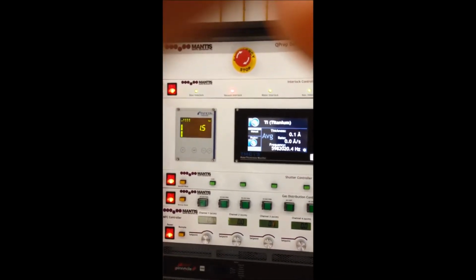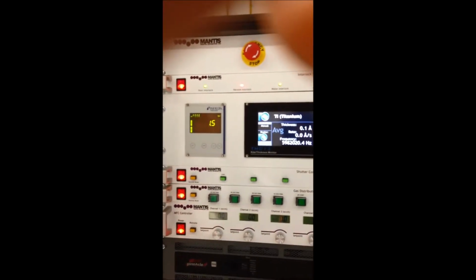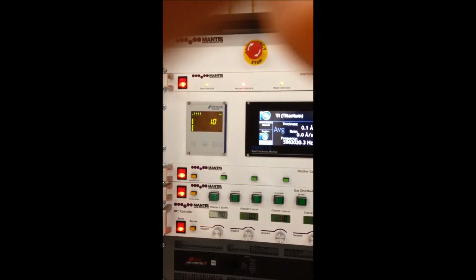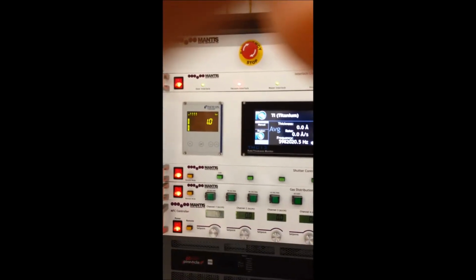If the water is not on, the turbo will still go on, and it's not interlocked. So you have to make sure before you turn on the turbo that you note this down, because if you don't have the water on, your turbo will overheat. It's water cooled, so water must always be on.